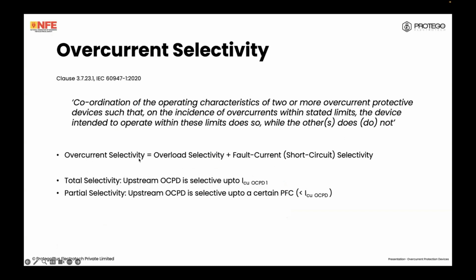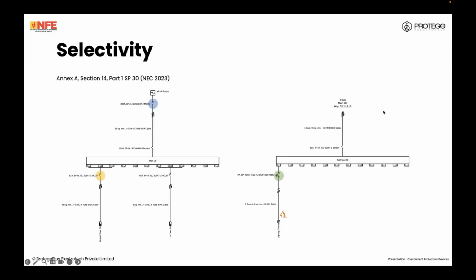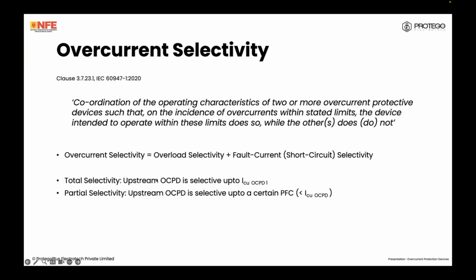Now, overcurrent selectivity. Overcurrent is made of overloads and fault currents or short circuits. Therefore, overcurrent selectivity is made up of overload selectivity plus fault current or short circuit selectivity. When we talk about selectivity, either we have total selectivity, which means the upstream OCPD, so if there's a fault here, will not trip for all values up to Icu of this. So if there are faults up to Icu in this circuit, only this breaker will trip. This breaker will not trip. So total selectivity is achieved up to the Icu of this circuit breaker or overcurrent protective device.